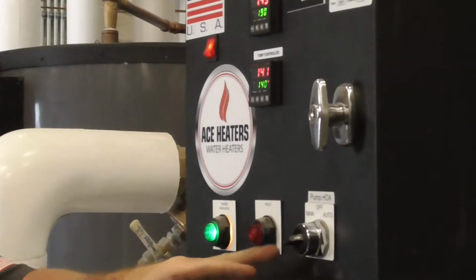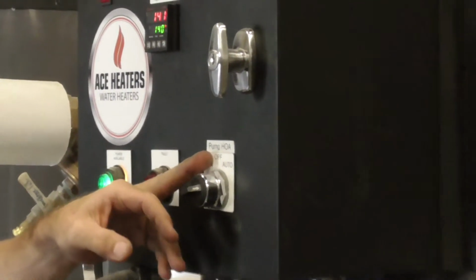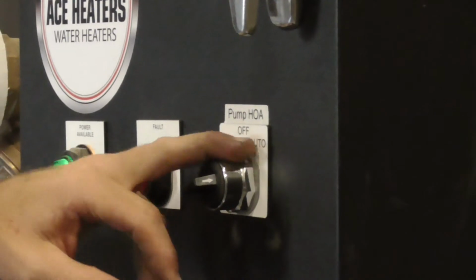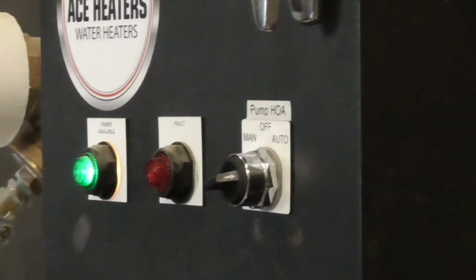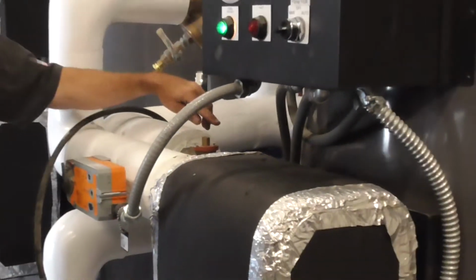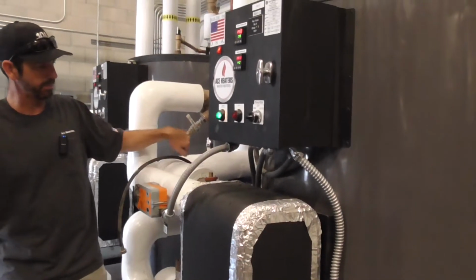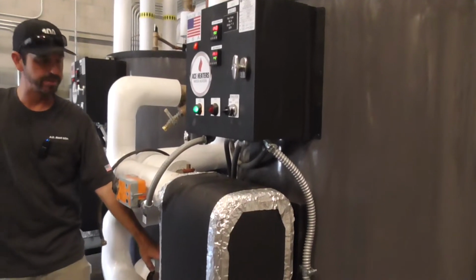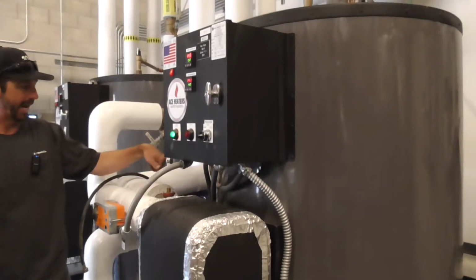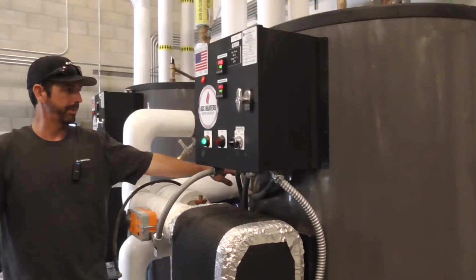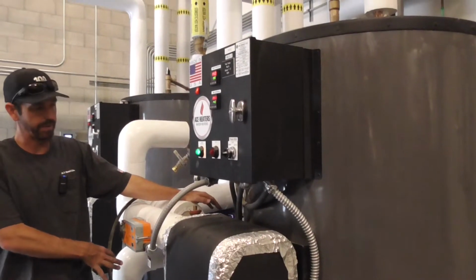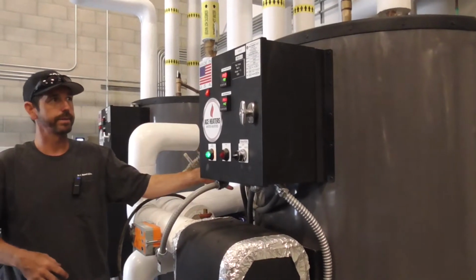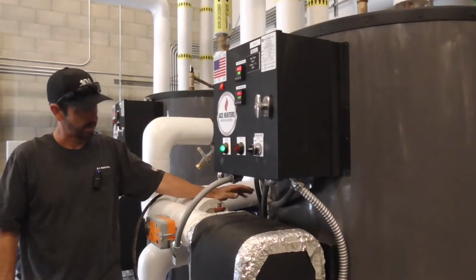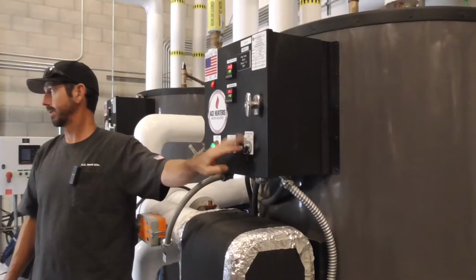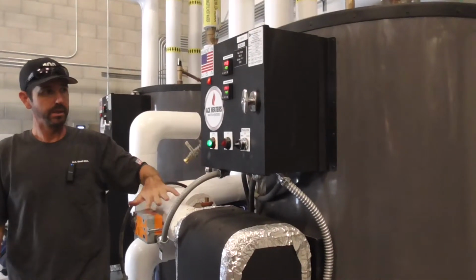After that, this is important that you understand that this HOA manual off auto switch is only for the pump control down here. So we are pumping water out of the bottom of the heat exchanger, pushing it through the heat exchanger at the bottom on the domestic side, and then comes out the top and back into the upper part of the tank. So without the pump running, we won't be making hot water. Okay? And that's controlled off of this switch right here. This switch has nothing to do with the control valve.